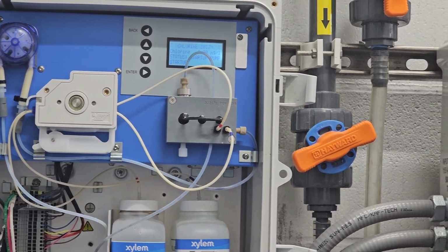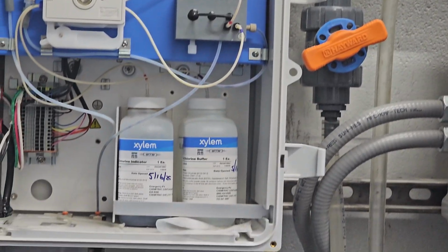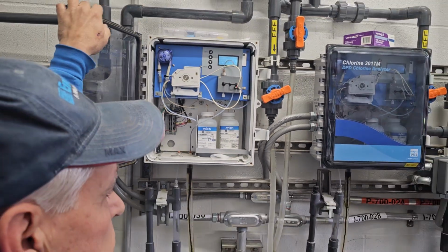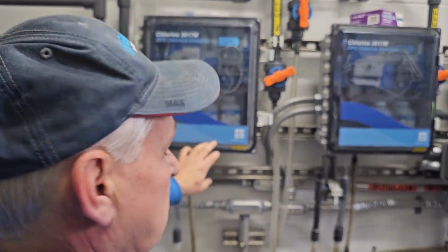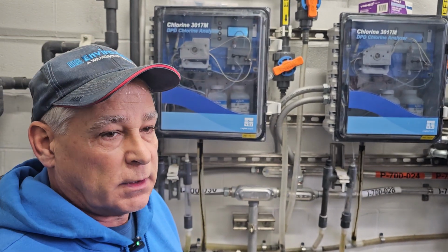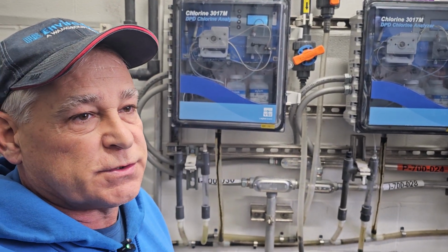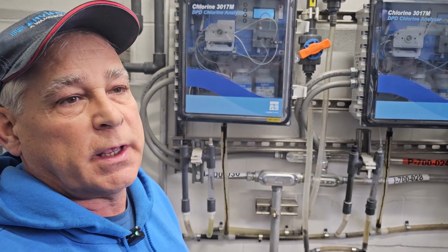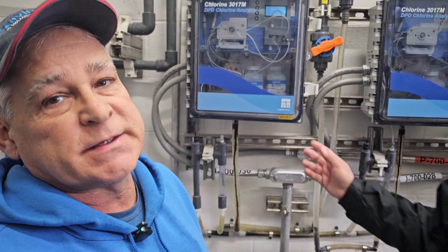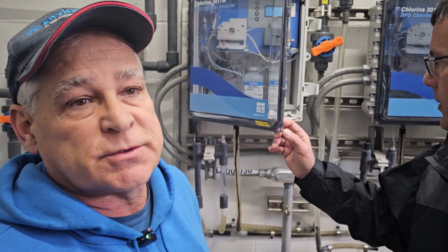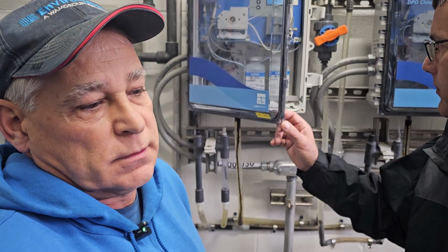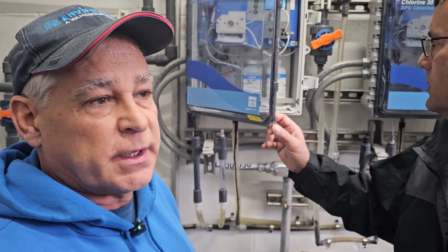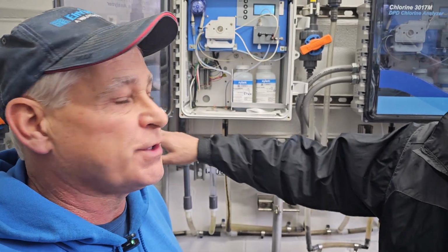I would just make sure you shut down with clean, fresh reagents. How long do the reagents last for? One month, yeah, one month. And like we were talking, these instruments are typically running and you use the reagents up before that time expires. But in this case, because it's storm water only and it's intermittent use, you're going to have to keep an eye on that and make sure you've got fresh reagents.